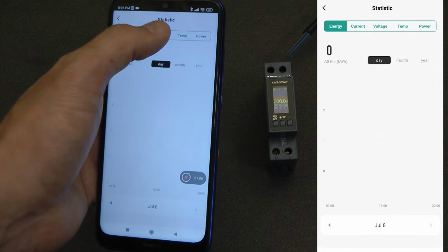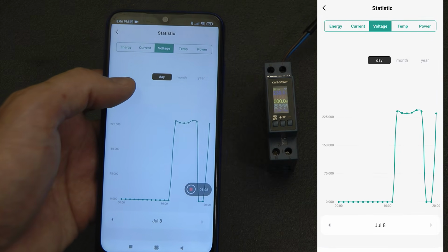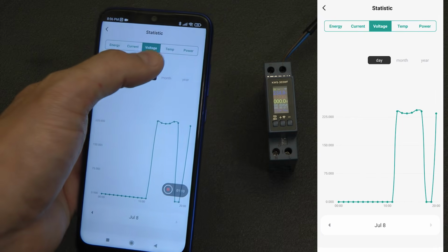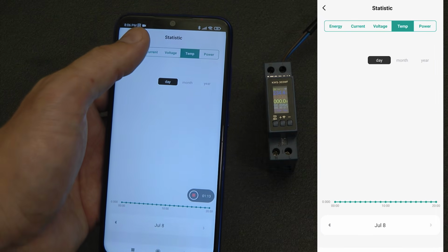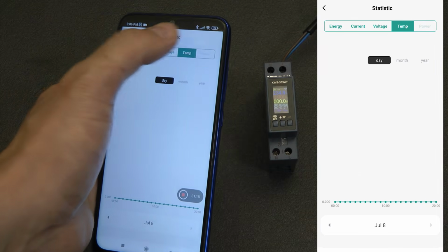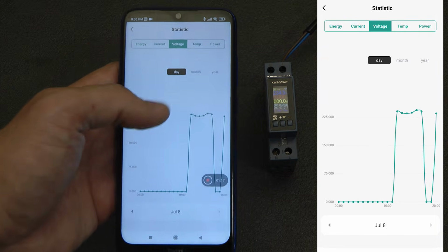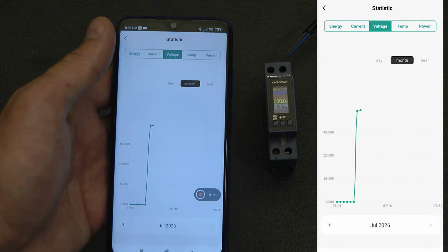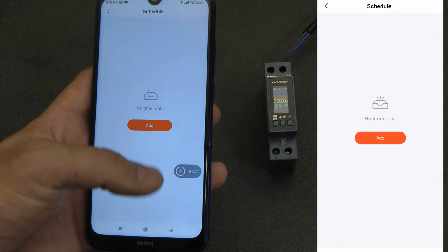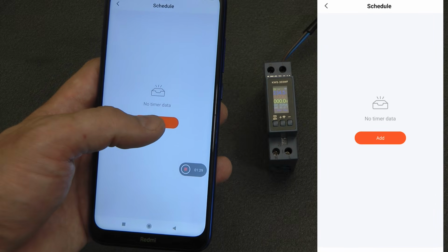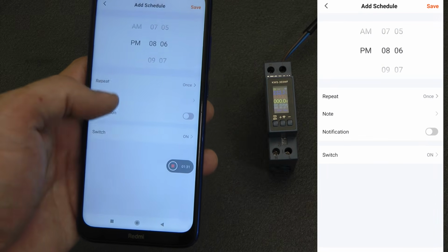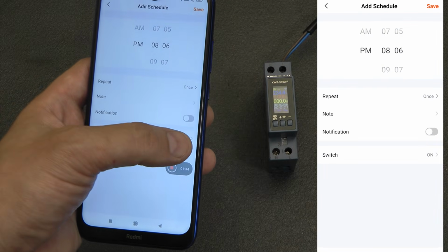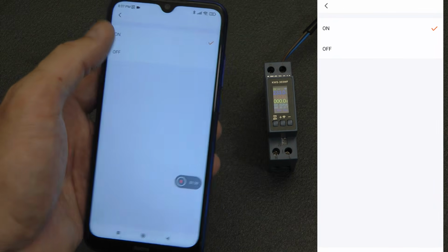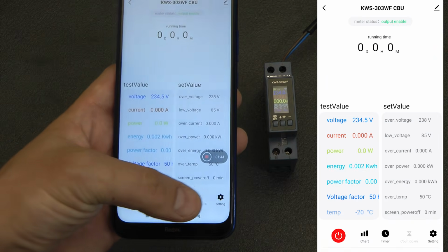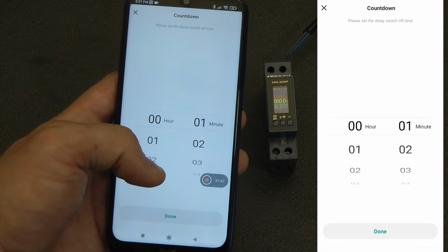The next section is graphs. Here you can view statistics by day, month, or year for 5 parameters: electricity consumption, current, voltage, temperature, and power. This is really convenient for load analysis. There are also timers. You can configure automatic switching on and off, for example, to start a consumer at night during the cheaper tariff and turn it off during the day. There is also a regular countdown timer. After the set time, the relay will turn off the load by itself.